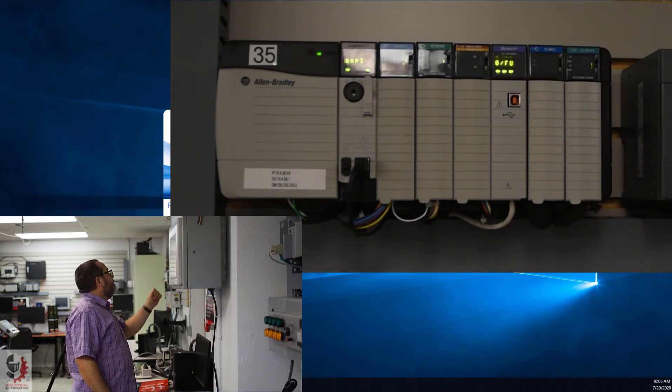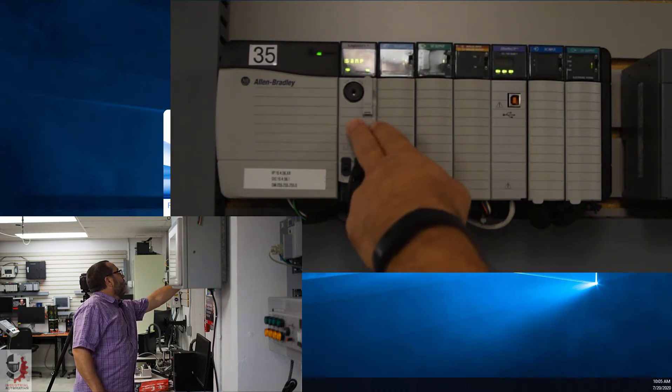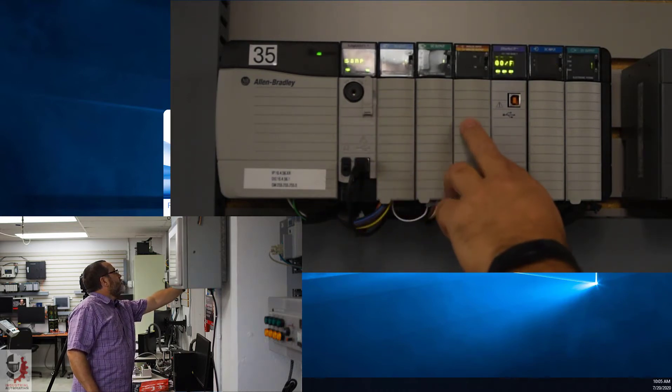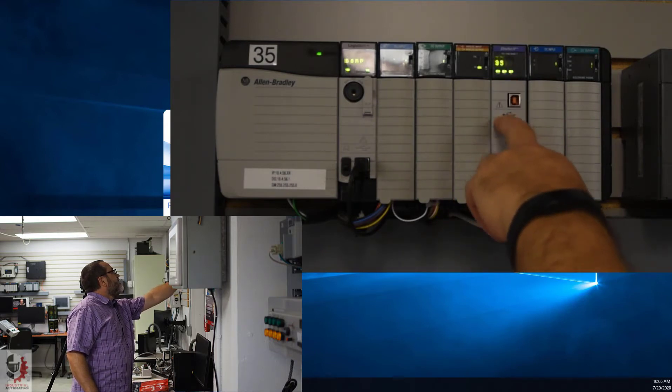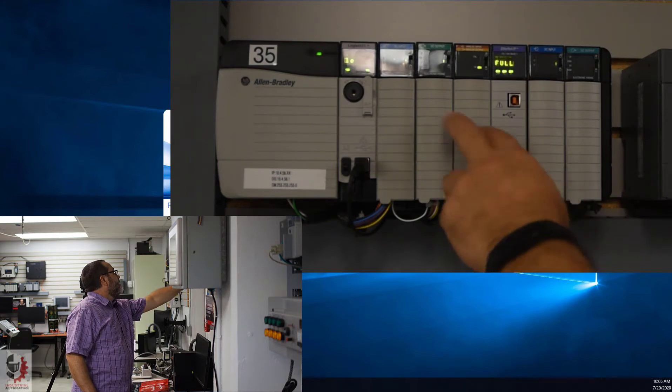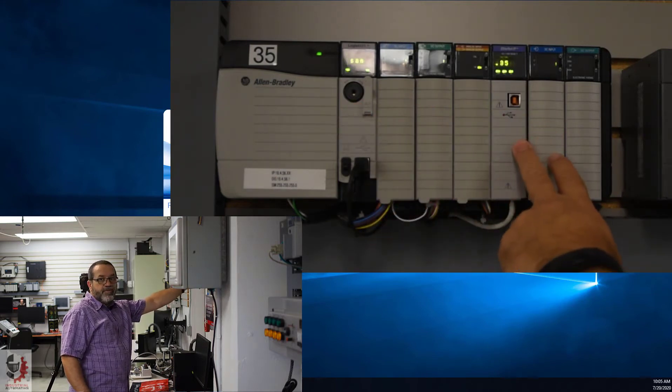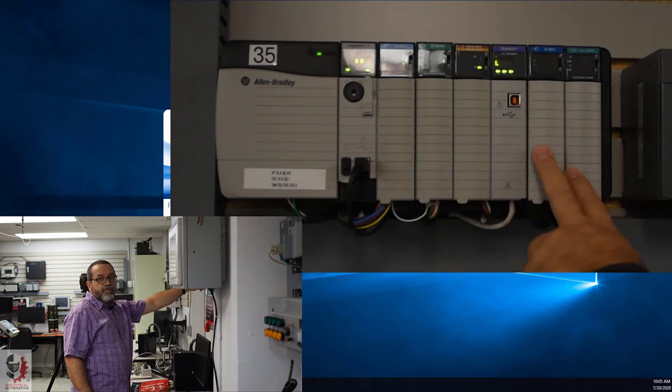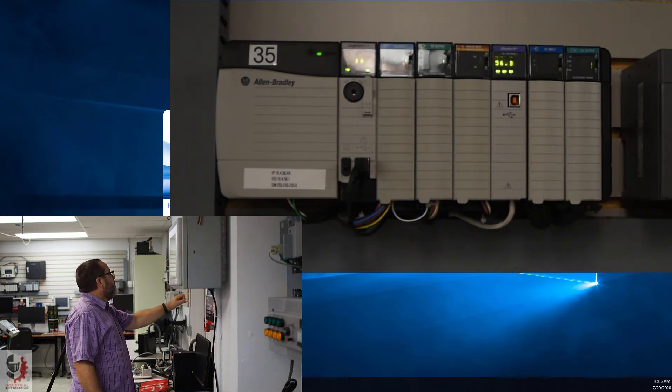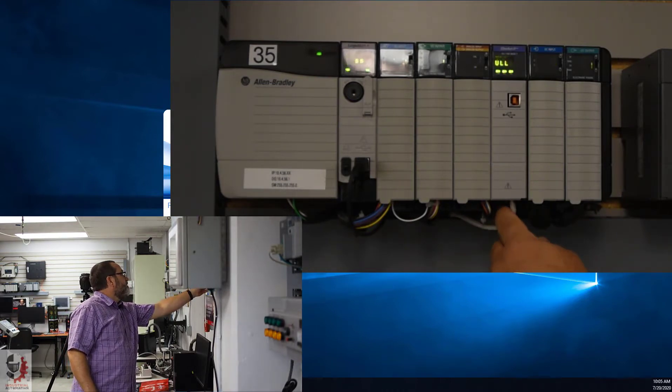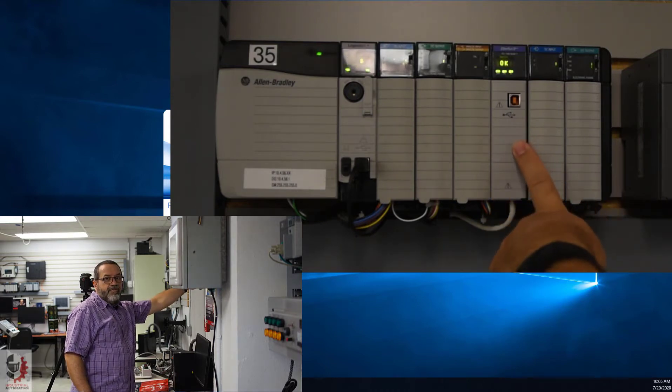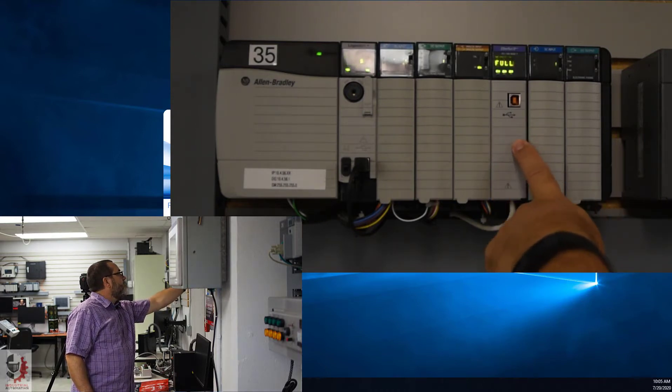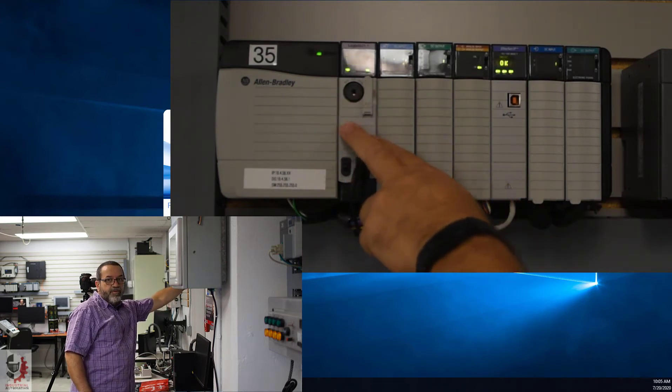And let's see what we've got here. We've got our controller in slot 0, and we've got some inputs and outputs, analog. We've got an Ethernet IP communication card in slot 4. And then we've got a few more inputs and outputs. Now to talk to this PLC, we're talking over Ethernet. So here's our Ethernet cable. That talks to the communication card, which talks to the backplane, and the backplane talks to the controller.